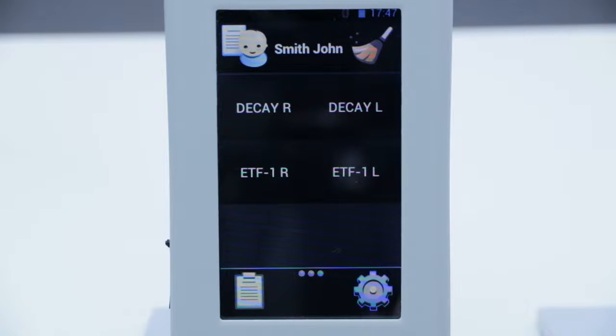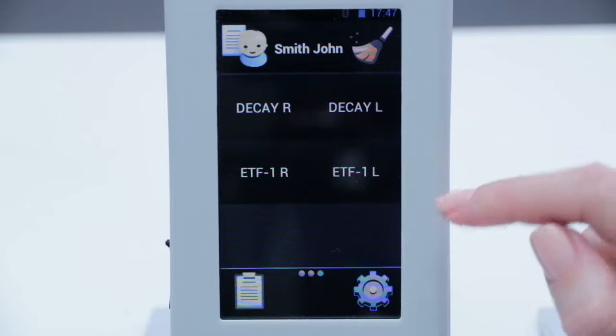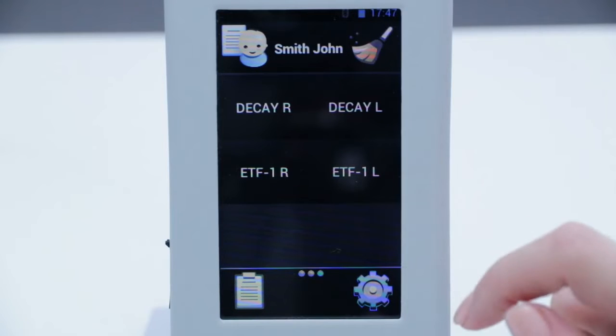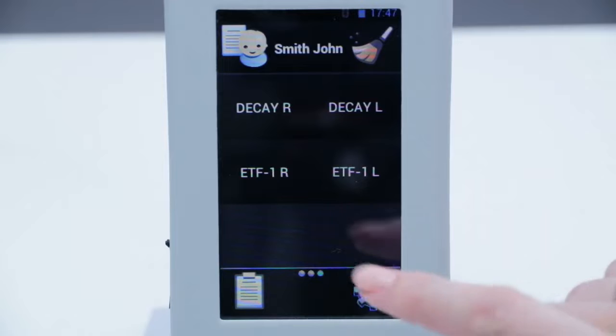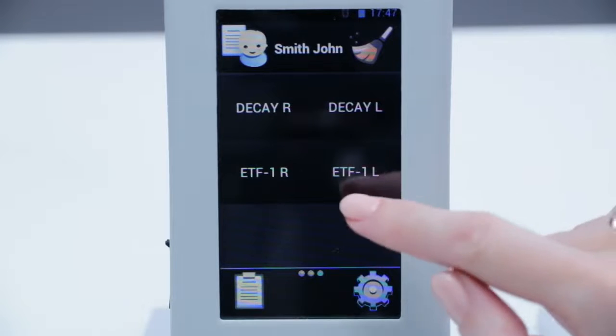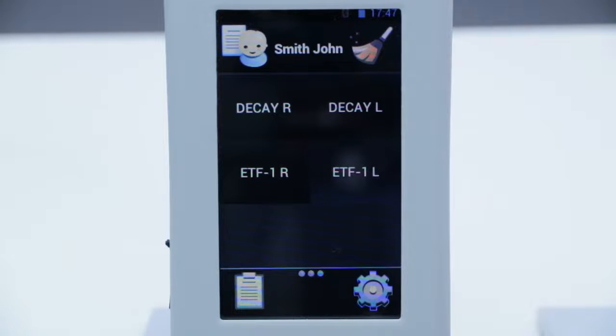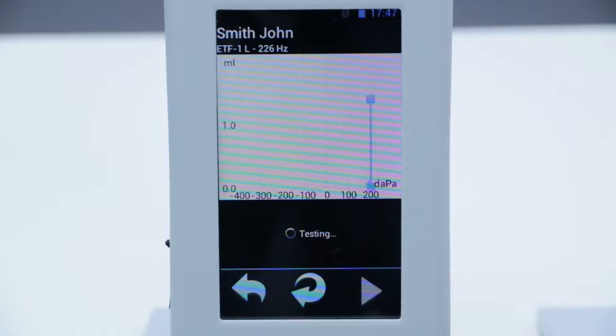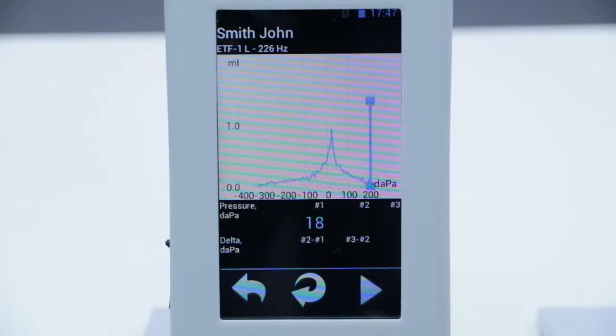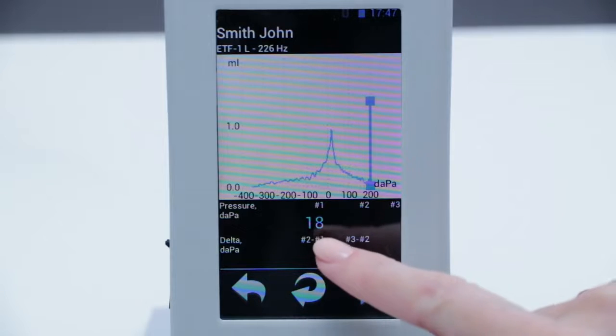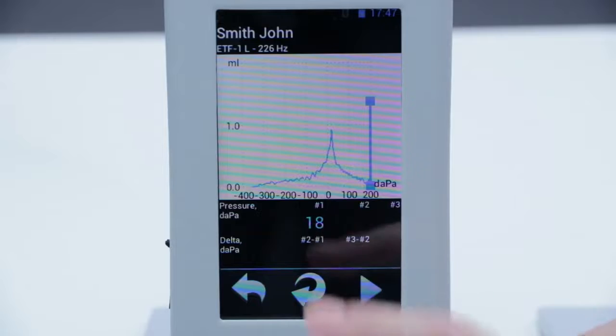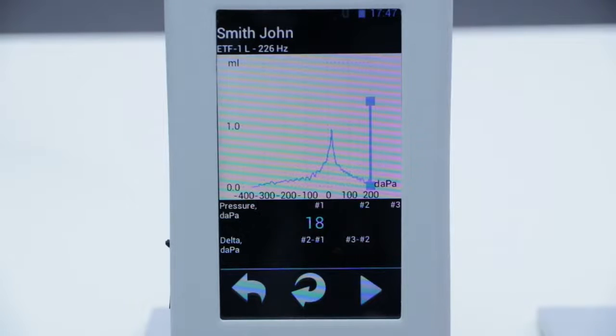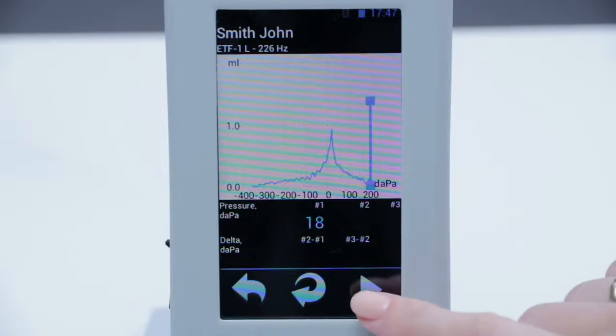To perform the Eustachian tube function test of the patient with intact tympanic membrane, we choose the side and push. The device will automatically register the tympanogram on the relaxed patient firstly, and we can see here the pressure of peak of this tympanogram.